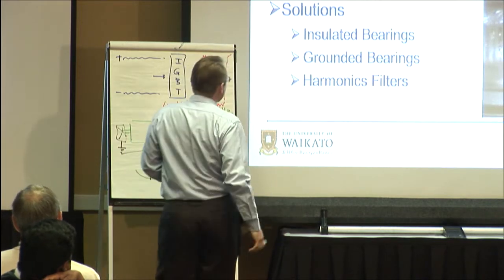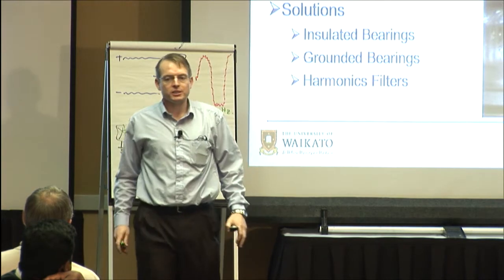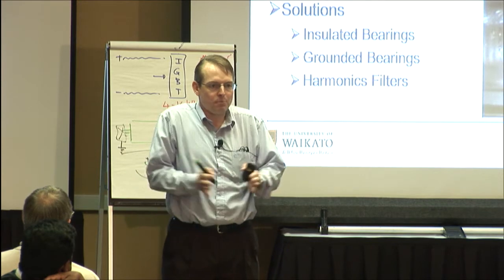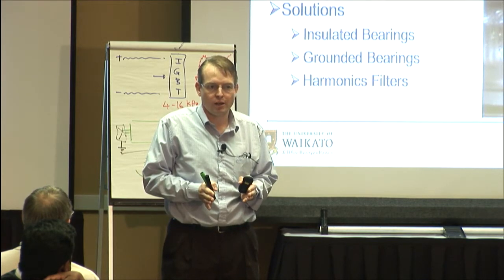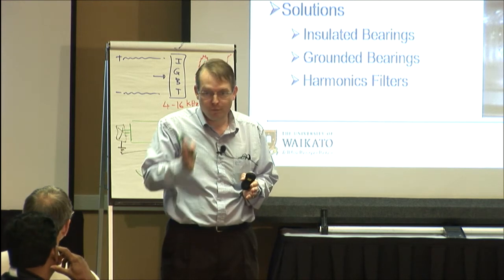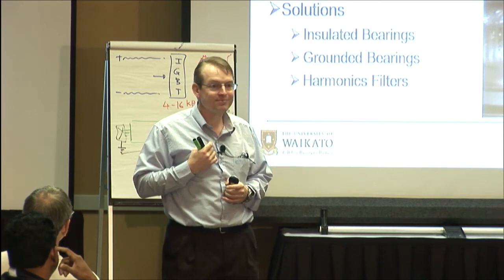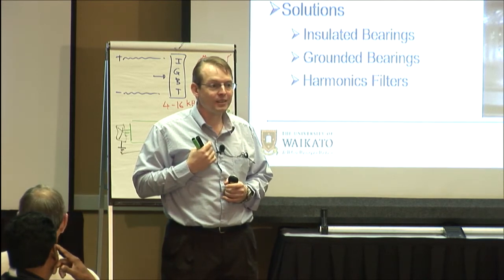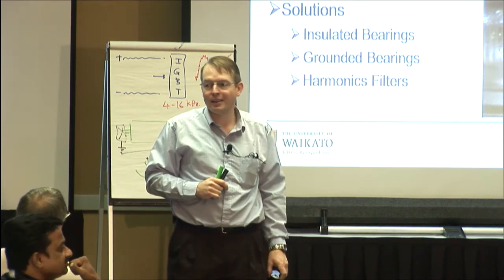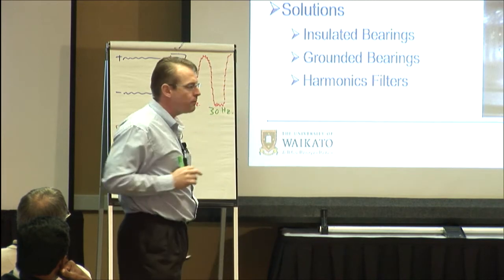Now, bear in mind, that's very much the Band-Aid. Because the ultimate thing we should be trying to do is limit the build-up of potential on the shaft in the first place, right? And how do we do that? The filters. Why don't filters get installed? Money, cost, right? So it's back to, hey, hang on, we've got to do this properly.